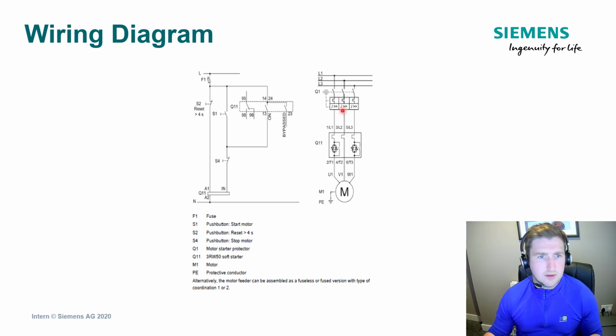And typically if you've got the fusing which is costing more than the soft starter, the more viable option would be to use the 3RV motor starter protector instead of semiconductor fuses to protect the internal components of the soft starter. So how does this work?